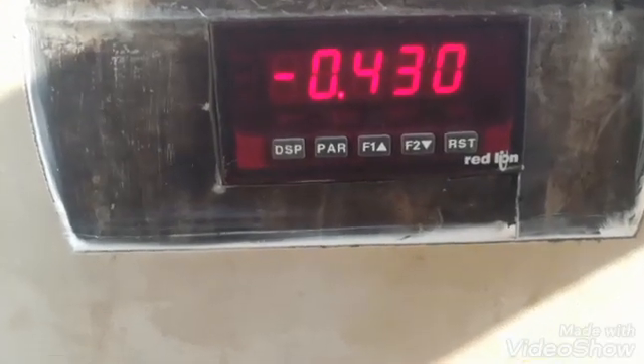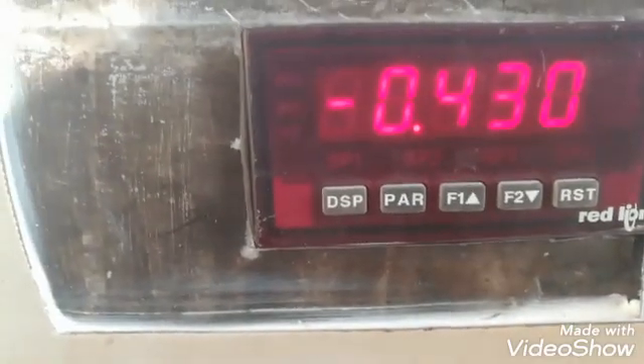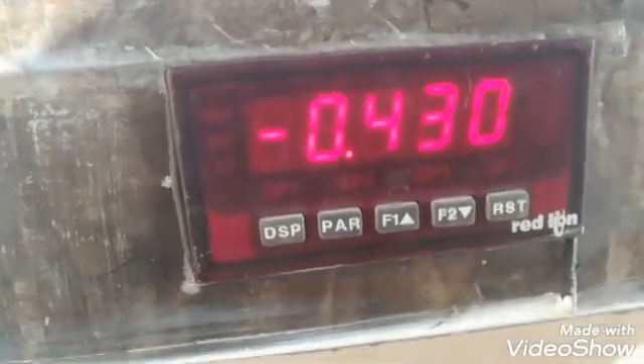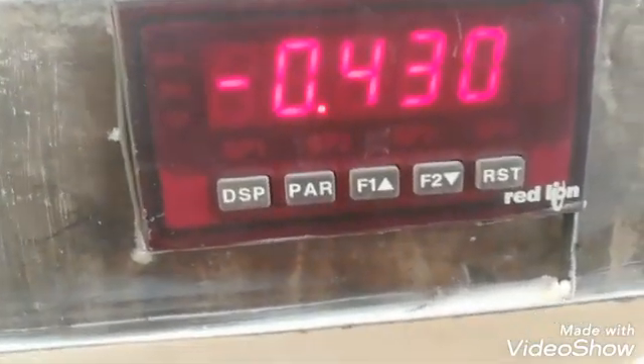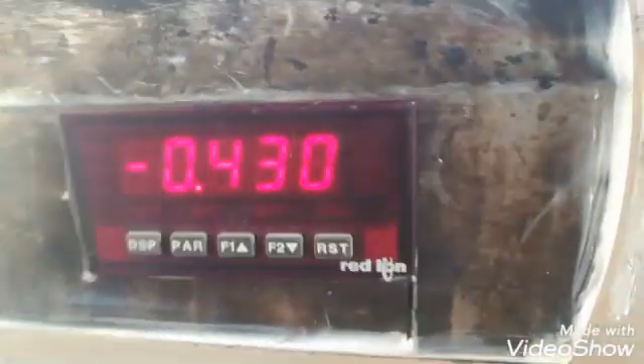Here you can see a weighing indicator — this is the Red Lion PAXS model weighing indicator. On the display you can see it's showing the load in tons, currently showing minus 0.43. We will adjust it to zero.